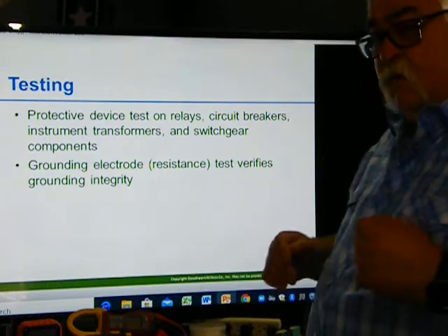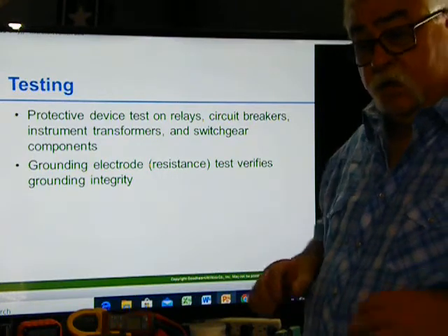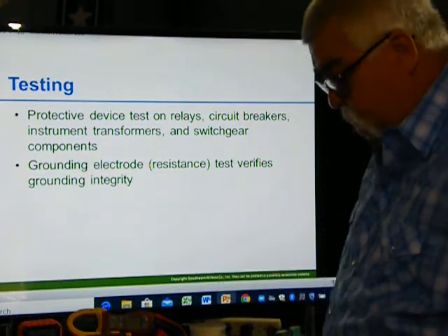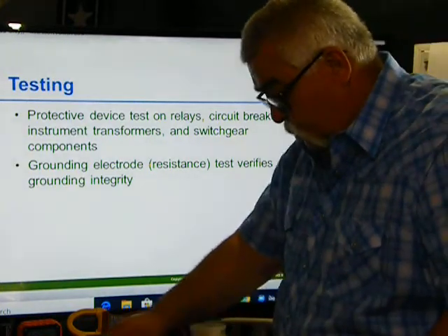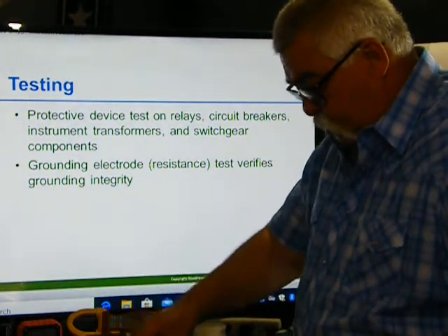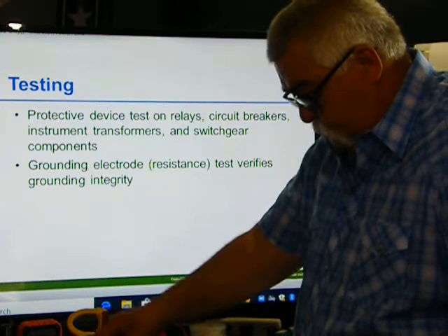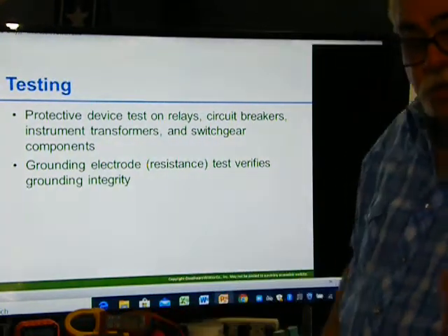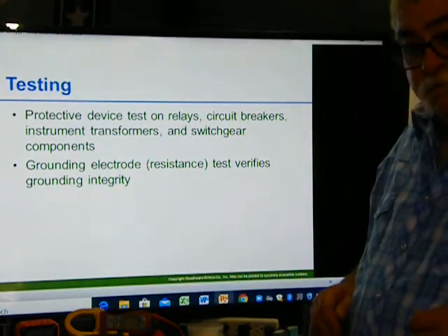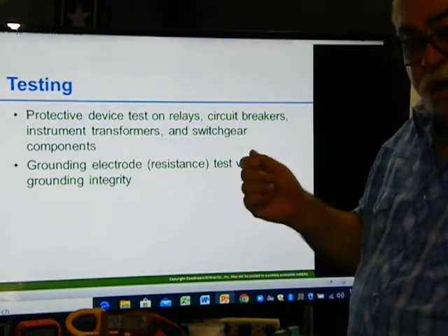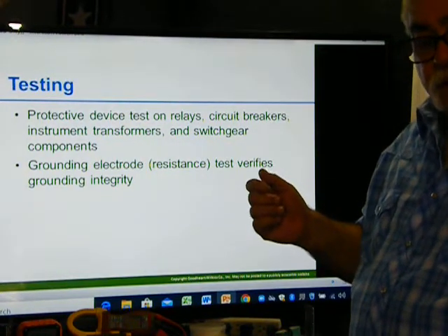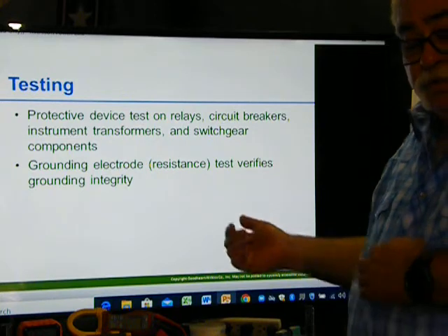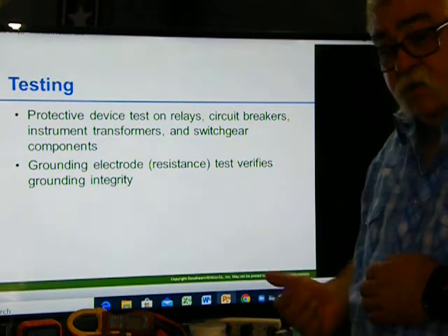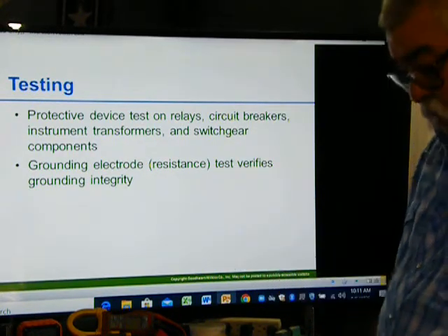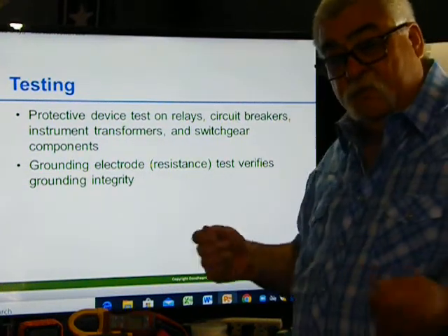You want to make sure that you have a good solid ground on things. So you have to make sure everything was in. Yeah, I told you where they had a problem. They got called into a chicken farm because the chickens weren't laying eggs. And so we went there and we started testing, and from the metal cage to the ground, we're getting like 3 or 4 volts. So why weren't the chickens laying eggs? They were getting shocked. You know, they're in the metal cage on the metal floor. So there was a difference of potential.